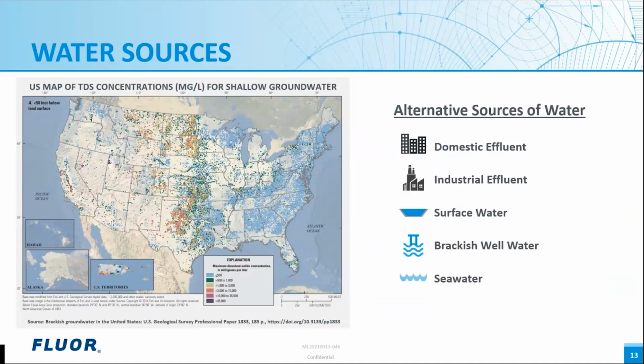Freshwater sources, as shown in blue and green, are generally designated for potable water through stricter regulations. Industries can evaluate alternative sources of water that can meet their needs. Surface water is another important source that can be considered, and the TDS levels are expected to be comparable to the ones depicted on the map. Domestic and industrial effluent are becoming more available as a viable source, and coastal areas can consider seawater if other sources are restricted. In coastal areas, such as South Florida, saltwater intrusion can increase groundwater TDS over time. So these types of risks shall be considered closely in the planning phase of projects when evaluating different water sources.